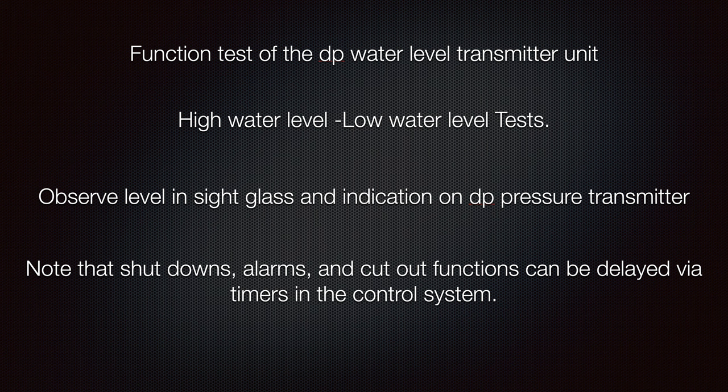Function test of the differential pressure water level transmitter: high water level test, then low water level test. Observe the level in the sight glass and check the indication on the differential pressure transmitter at the same time. Note that shutdowns, alarms, and cut-out functions can be delayed via timers in the control system. The timers can be adjusted, but normally you should not do that, because the manufacturer set them before the boiler was commissioned.